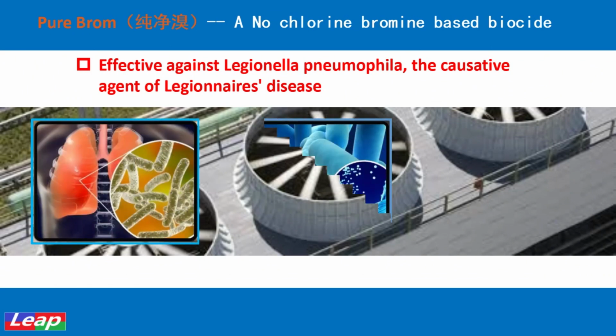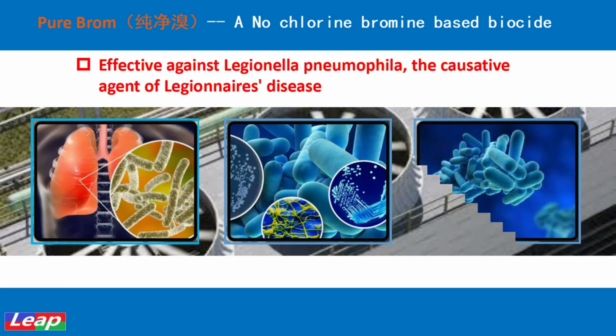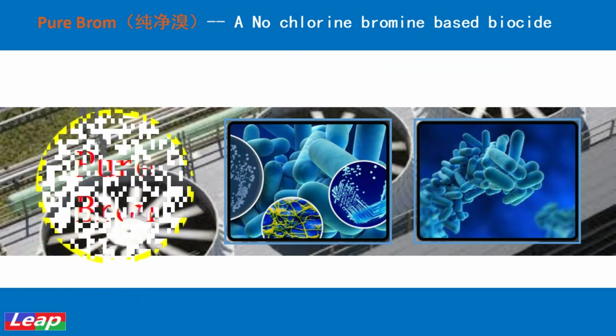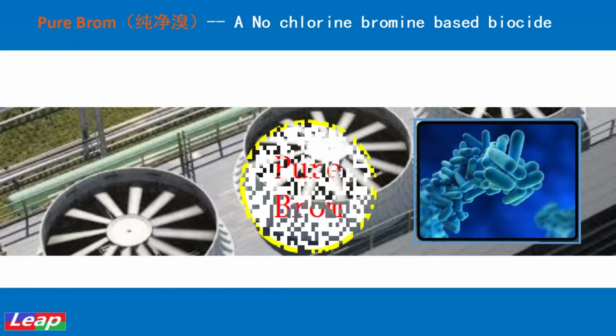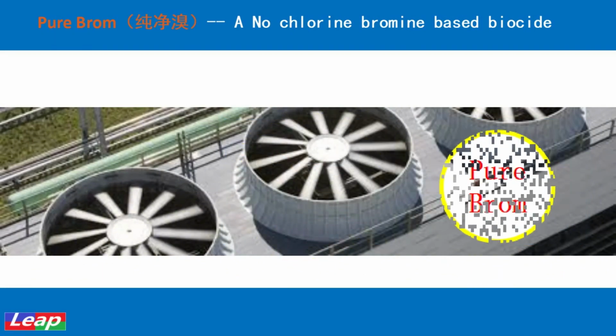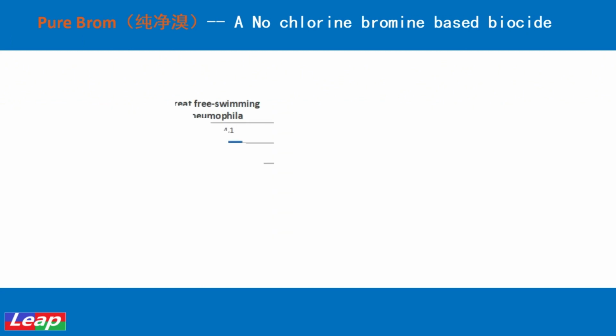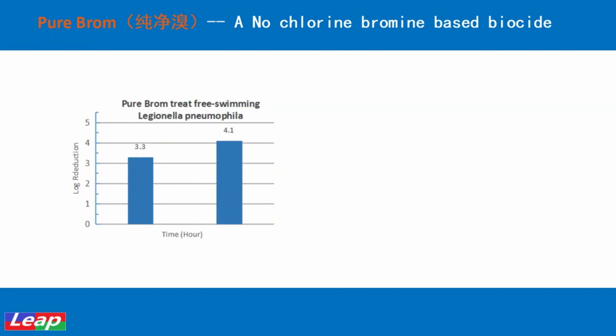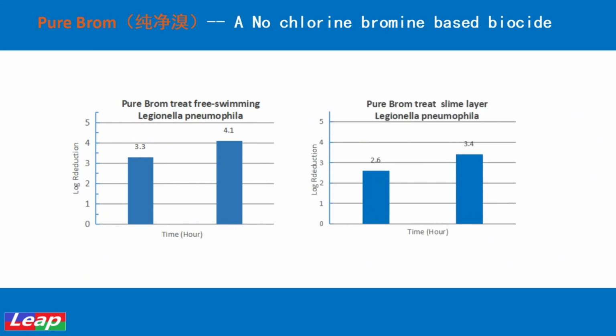Oxidative treatment, conducted continuously or intermittently, is a common method for cooling towers or water systems to combat Legionella pneumophila. Pure Brom is highly effective in killing Legionella pneumophila, disrupting bacterial cell membranes and inhibiting enzyme activity. Practical tests have shown that adding Pure Brom with an effective bromine dosage of 5 ppm can reduce the number of planktonic Legionella pneumophila by 3 to 4 orders of magnitude, and decrease the number of biofilm-attached Legionella pneumophila by 2 to 4 orders of magnitude.